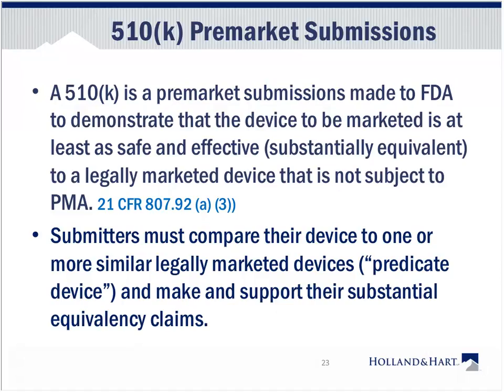We do this a lot. So what this entails is, say I'm working with a provider group that says we have come up with a particularly good kind of knee brace, and we want to distribute it. The first question you have to ask is, what kind of clearance is it going to require from the FDA? Is it an exempt device? Is it a Class 1 or a Class 2? If it's either one of those, is it exempt from a 510K? And if it's not exempt, is there another device that is already out there with FDA clearance that it is substantially equivalent to, such that we do not have to do anything other than show that our new device is substantially equivalent to a legally marketed device? And by legally marketed, I mean already has received FDA clearance. I hope that makes sense.